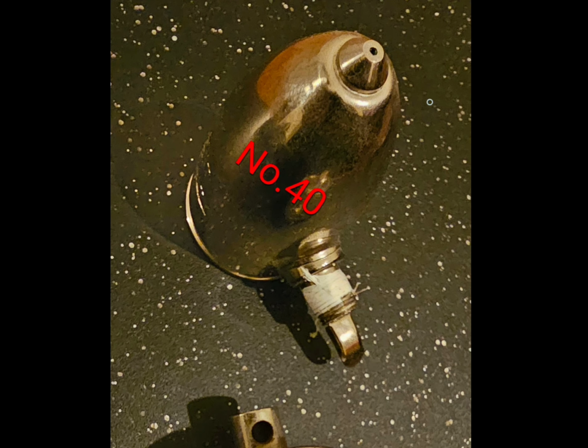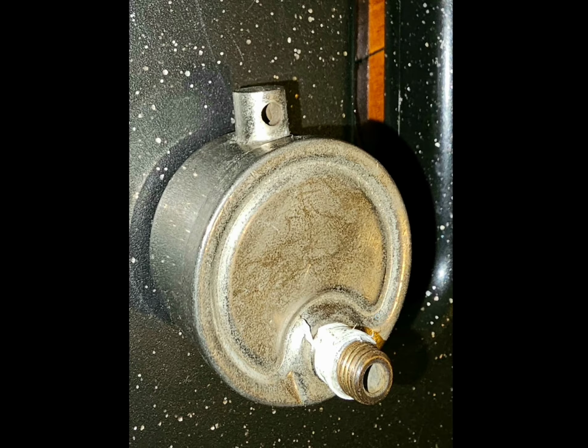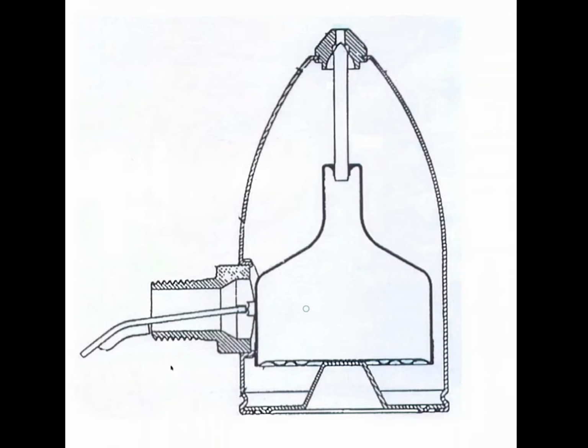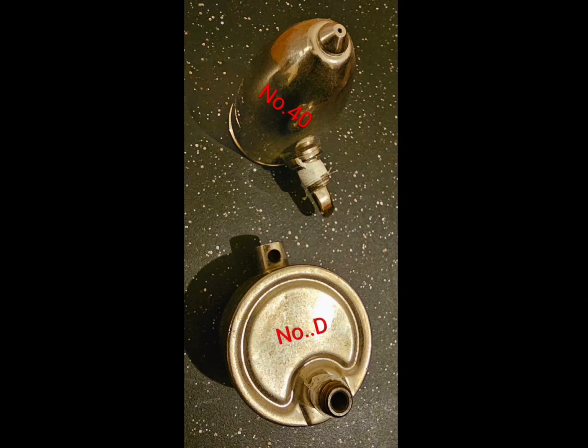Here's a reason why, or better yet, have you ever tried blowing through one of these? Which I have, and I've saved you the trouble of doing so in case you want to find out. But have you ever tried to blow through one of these? How much air do you think you can push through this opening? As a matter of fact, you probably would hurt your face trying to squeeze enough air through this thing, trying to push this float, this thermostatic pin, into the lock position. You would probably hurt yourself.